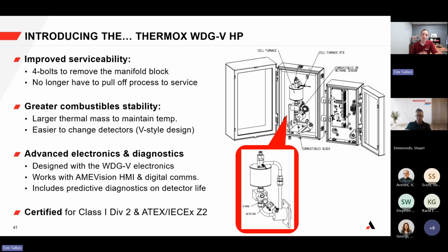What's better about it? I mentioned improved serviceability. You can see those 4 bolts right here, and you can take out that entire manifold block. This is the manifold block. In the previous generation model, you would have to take the whole analyzer off the process in order to service it. Sometimes the analyzer weighs 30 pounds, sometimes 55 pounds, sometimes more than that. That can be a challenge, especially in a high particulate application. So serviceability is improved, built off this 4-bolt pattern for the manifold block to make it easier to access.